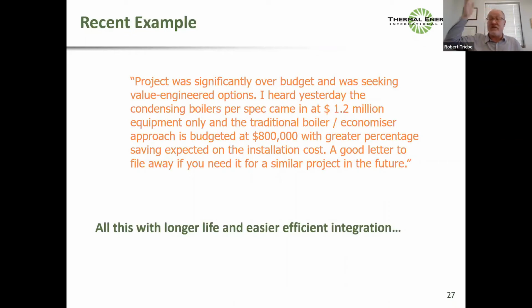The project was over budget. This was a project where people were looking for a condensing boiler. And the condensing boiler project was significantly over budget. They were looking for a condensing indirect boiler, and they were seeking value engineered options. The condensing boilers per spec came in at 1.2 million, and the traditional boiler economizer approach was at about 800,000 with longer life and likely better performance. So yeah, that's an example, and this is why I'm so hard on this one point.